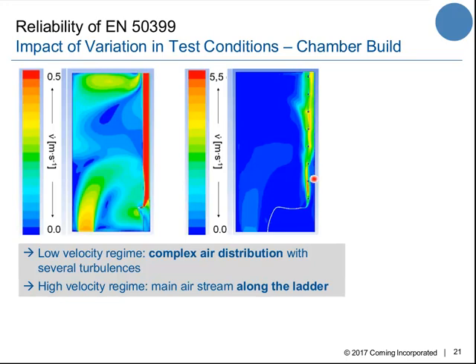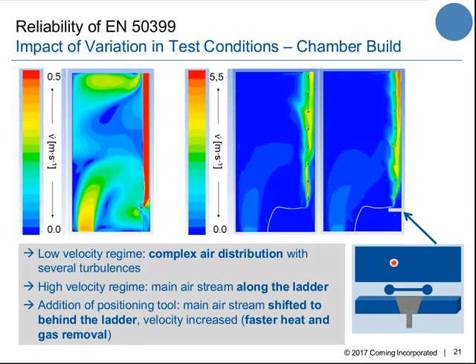So what one might think about is just a baffle in the back here as a contact point for this ladder to ensure always the correct position. So we simulated this kind of baffle, and what we found is that now the main gas stream in this high velocity regime is on the one hand shifted to the back wall away from the cable surface, and on the other hand the velocities are increased. So heat and gas are removed faster from the chamber and more away from the cable surface.